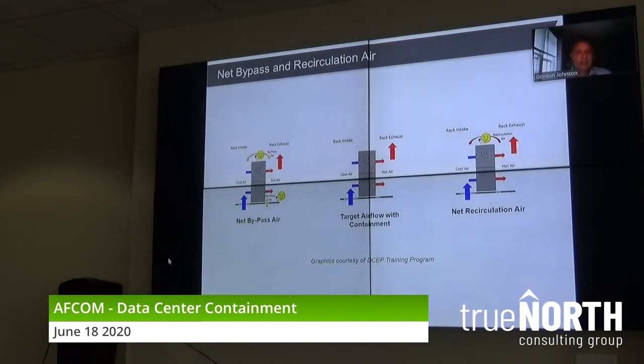But again, focusing in on the IT equipment, I don't want anything but that supply air temperature that I've set at my CRAC unit. That's the only air I want coming into the intake. The problem on the left: most people have net bypass air, and they always have bypass air if they don't have containment. Bypass air is just like its definition.